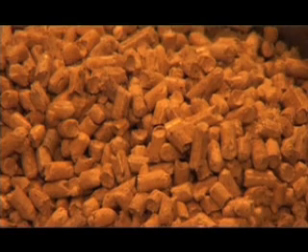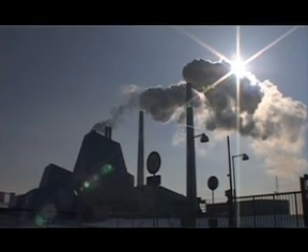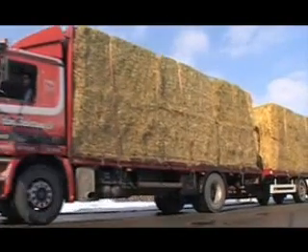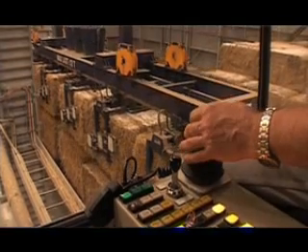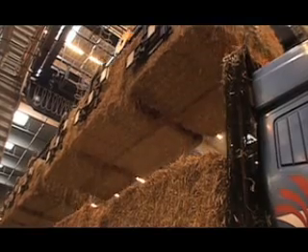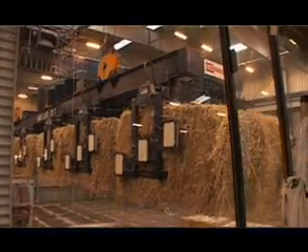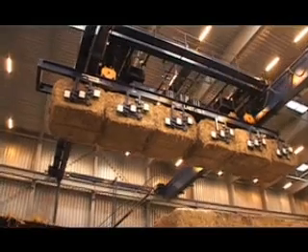It's produced from the chips from the manufacturing of hard floors. We take in about 85 tons of wood dust, which we blow into the boiler per hour. The other biofuel that we use out here is straw — large straw bales coming in from Danish farmers. They are not allowed to burn it in the fields. We have a policy in Denmark that the straw should be put into the power stations instead. We take in about 25 tons of straw per hour into a separate boiler, which can turn it into heat and electricity. Biomass is a CO2-neutral fuel.